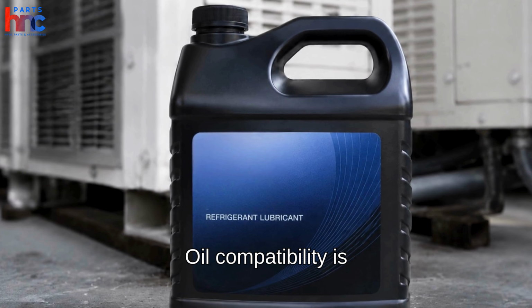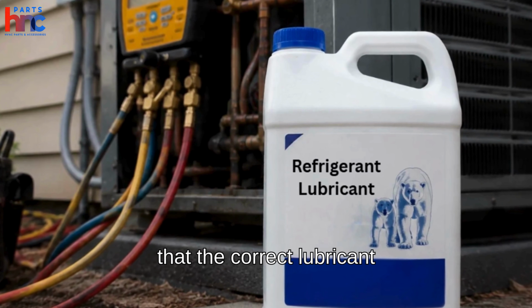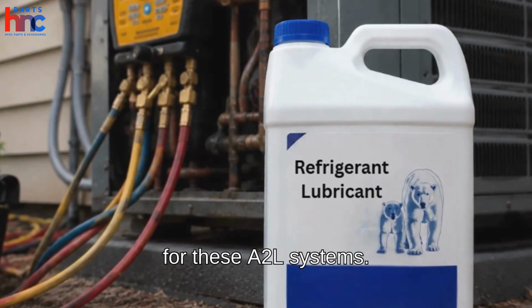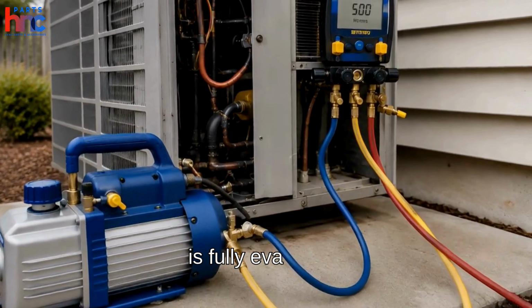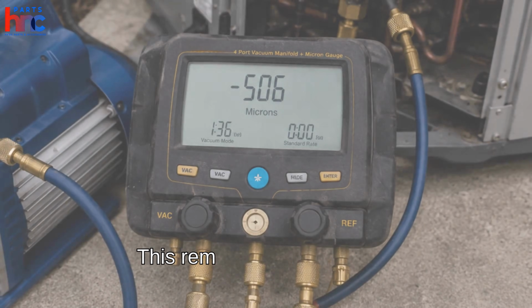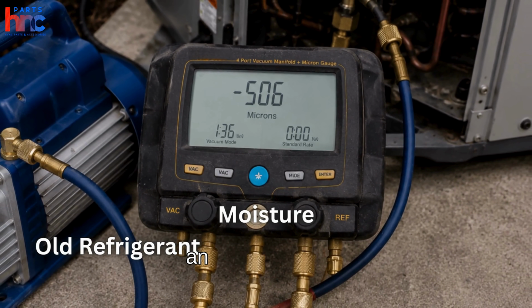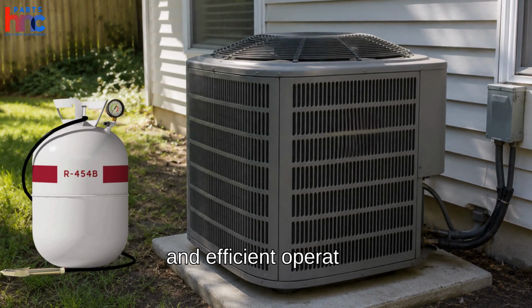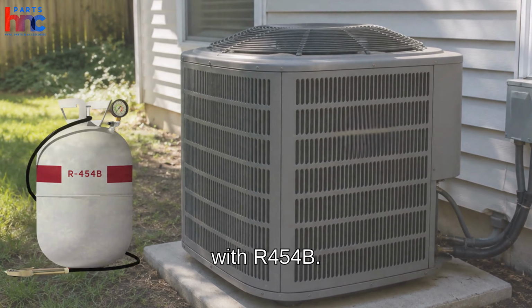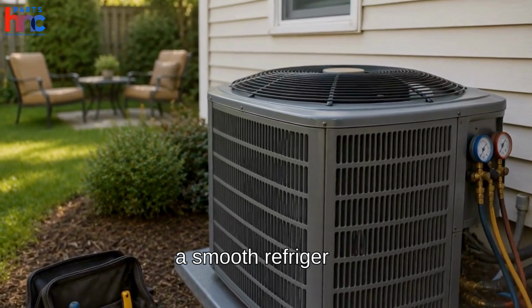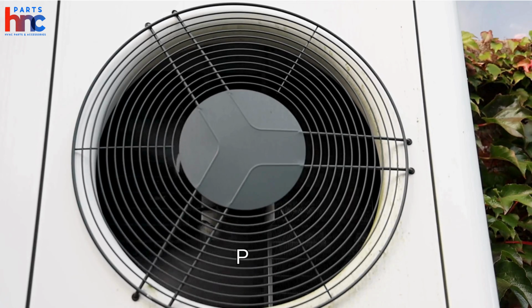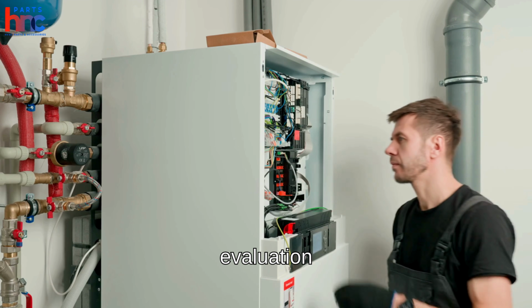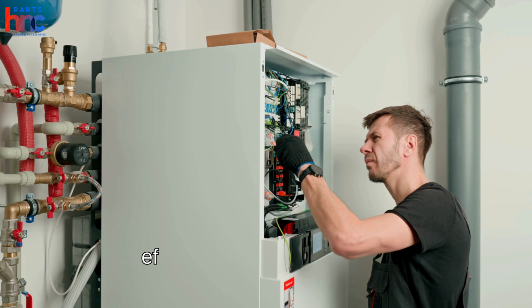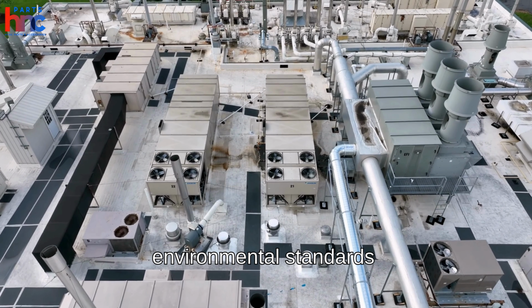Oil compatibility is another critical factor. The wrong oil mix can damage internal components, so technicians confirm that the correct lubricant is used for these A2L systems. Finally, the system is fully evacuated before recharging. This removes old refrigerant, moisture, and contaminants to ensure safe and efficient operation with R-454B. These steps ensure a smooth refrigerant transition without performance loss or equipment damage. Proper evaluation helps HVAC systems run efficiently and meet modern environmental standards.